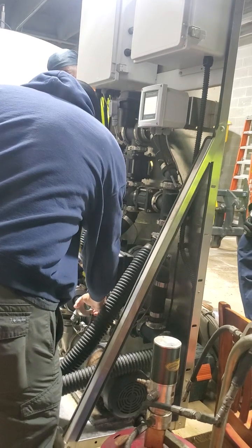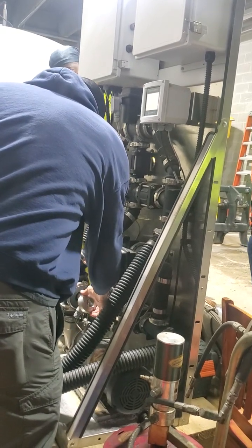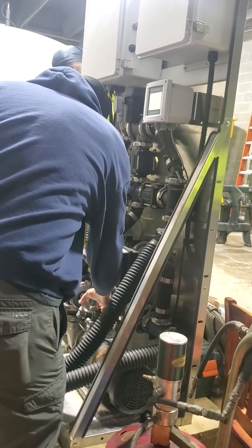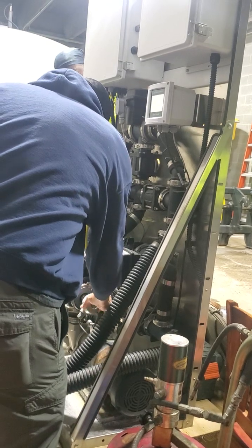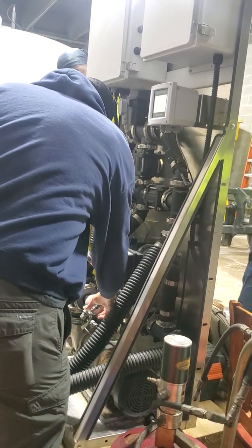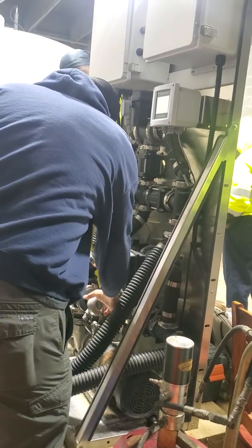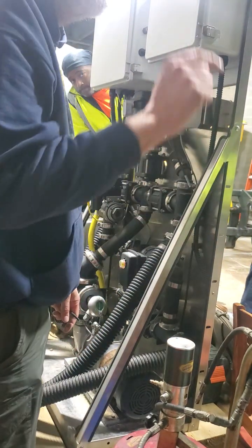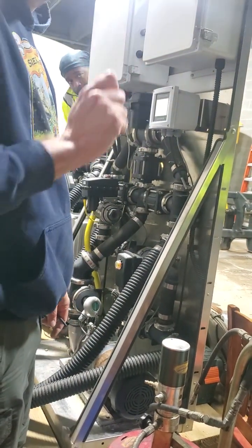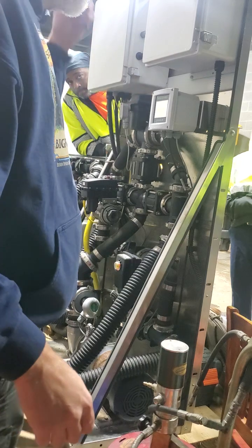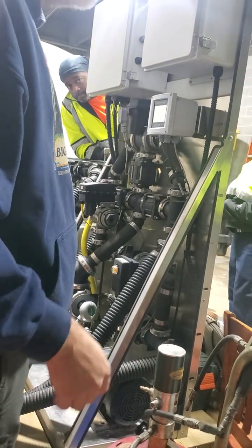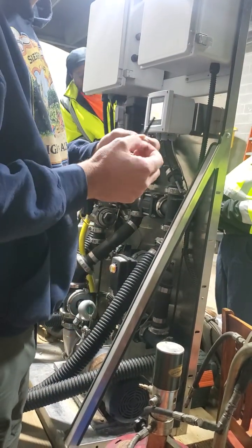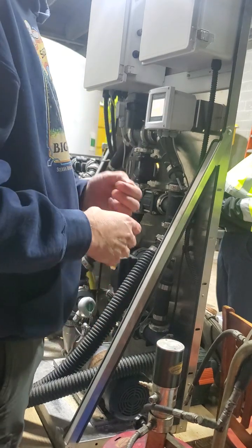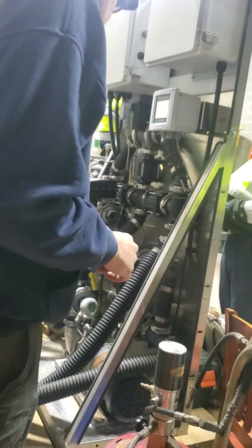How much power is in that? Nothing, it's 24 volts, DC power. So you can go in there and just tap the wire, see if it fluctuates or does anything to the concentration reading. Turn the machine off, re-strip the wire very carefully, and put it back in there. Self-explanatory.